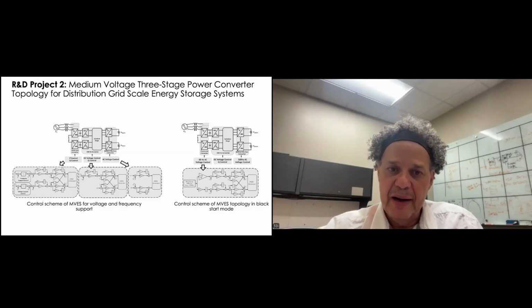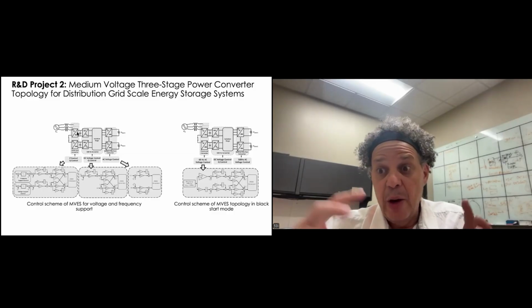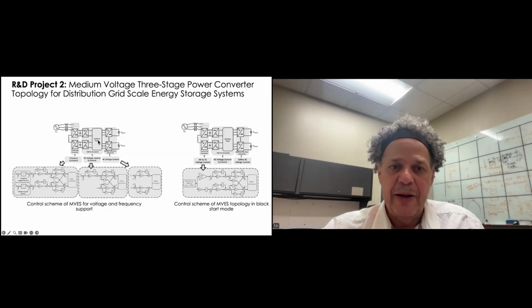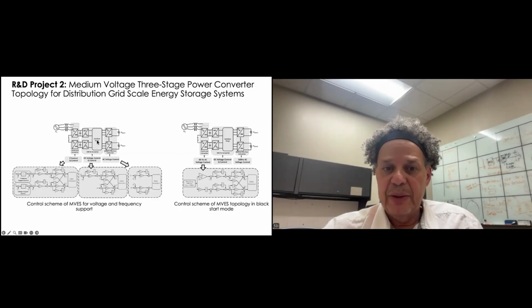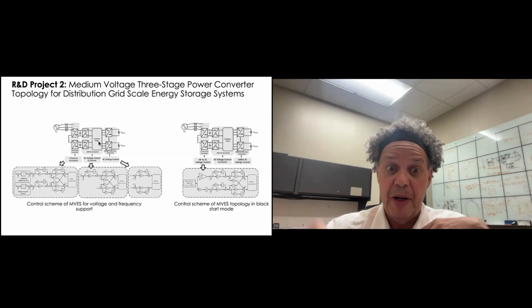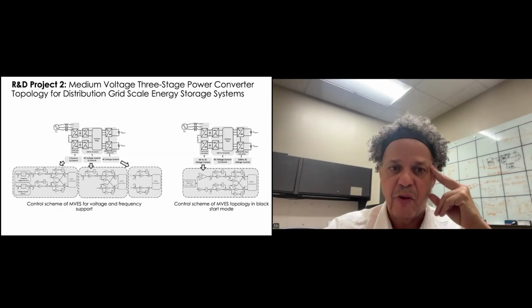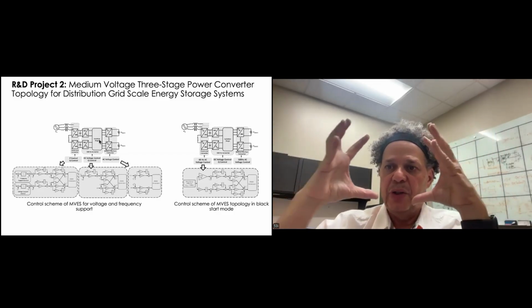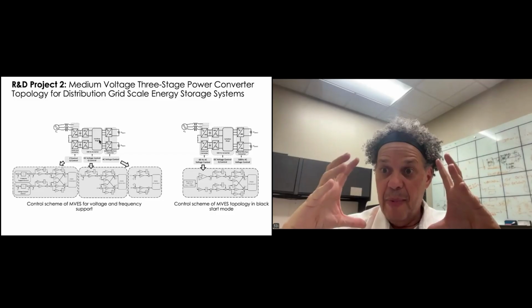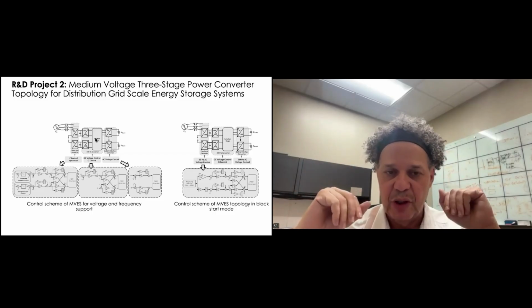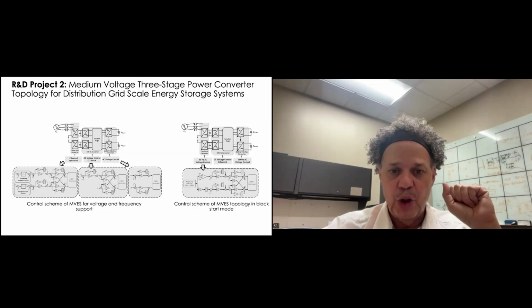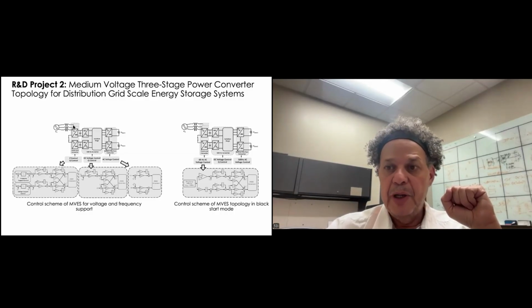For example, you can see here, I can put as many energy storage together as I want, so I can scale in power. And at the same time, I want to directly connect to the medium voltage using an isolation stage, which is not 60 hertz but a medium frequency transformer. So I have here a 600 hertz transformer, and what I gain when I use a medium frequency transformer is that I reduce the size of the transformer a lot, actually about 10 times the size, and I can manage to install this pretty much anywhere - faster, lighter - and connect directly to medium voltage AC of the feeder.